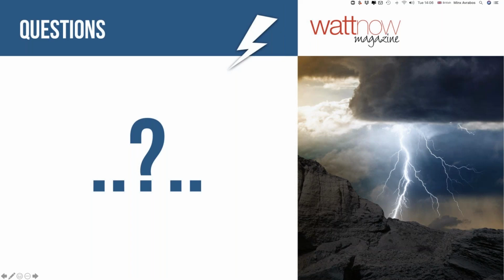In my example, I took a certain lightning current and assumed that the same lightning current is injected into a copper tape and also a brick building. Without injecting the same lightning current into both cases, I cannot compare the voltage developed in the two. So I don't know exactly what he's trying to clarify from this, because it's very simple: when the same current amplitude and waveform is injected into a brick column and a copper conductor of the same height, the voltage drop along the two is totally different. That's the idea.